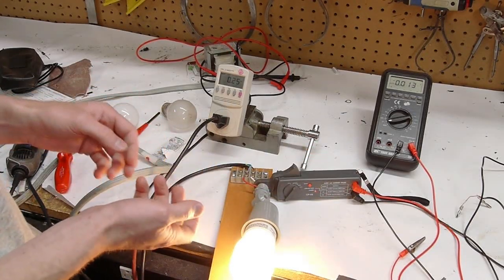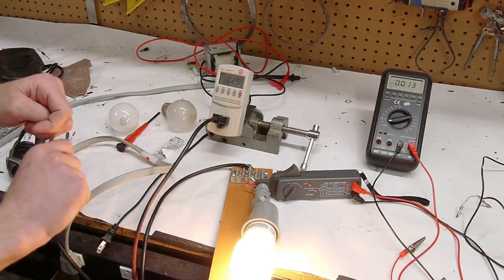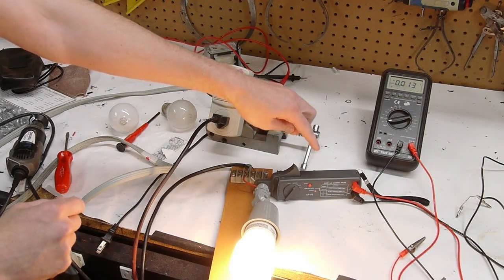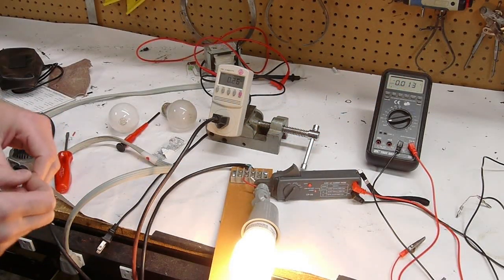So let's hook the probe up to the scope, which is really what this thing is useful for. If you just wanted to know what the value was, you could use one of those Extech clamp on meters that just has a readout right on the meter. The whole point of getting a current probe is to actually analyze the current waveform on an oscilloscope. So let's hook it up.